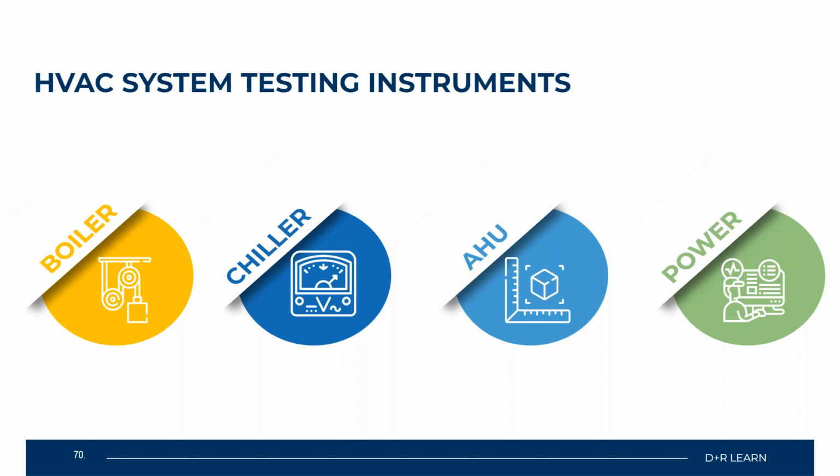I know I've been to many bases that have that. They have connection points for chiller systems where I could have a portable chiller brought in on a trailer, and then my team will connect the applicable hoses to that site, so that way they have chilled water still moving through their system while we clean the existing chiller. So scheduling and downtime is something that should be taken into account.